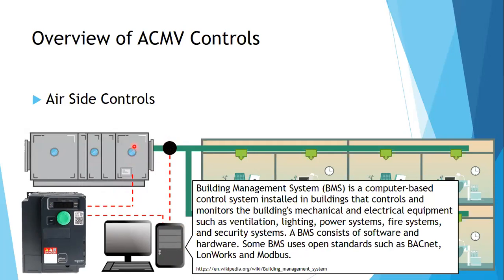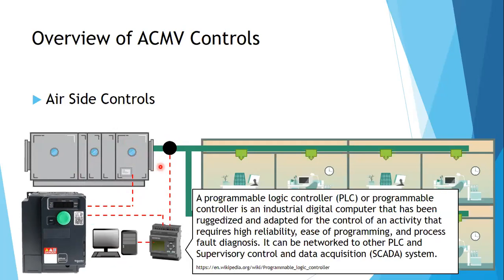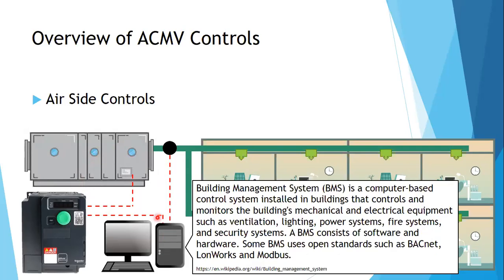Other things that are sometimes monitored by the BMS are the ventilation, the lighting, the power system, firefighting systems, and security systems. So not only the ACMV. If you're using a PLC, it is one piece, one unit, one PLC. But if you're using a BMS, not only your entire system, but other systems can go inside the system.